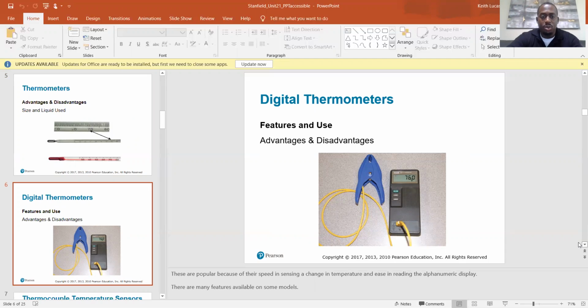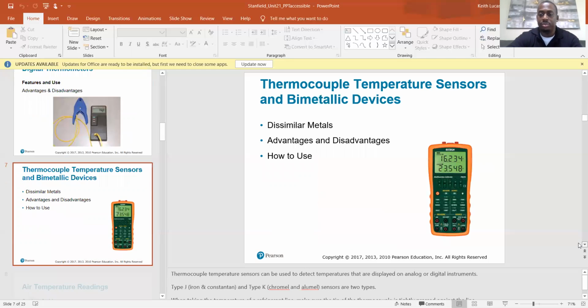So digital thermometers, these are popular because of their speed in sensing a change in temperature and ease in reading the alphanumeric display. There are many features available on some models. So this is the same type of electric thermometer that I have on my gauges, and a lot of you will have the same kind when you get your digital gauge set. They're the clamp-on types, so you just clamp that onto your refrigerant lines that you're measuring, and you'll get a temperature reading. So on here they have a digital thermometer that is plugged in, but as some of you already know, the digital manifold gauge set has a temperature function, so you don't need a separate digital thermometer. These plug directly into the gauges, and you'll read various temperatures, so you can get your superheat, subcool, or whatever.